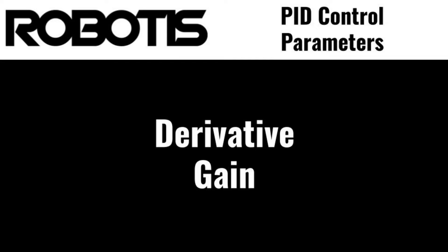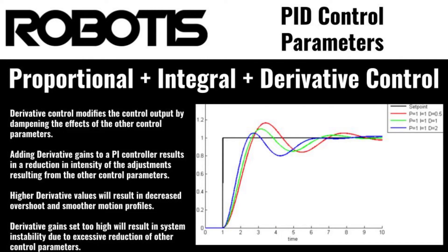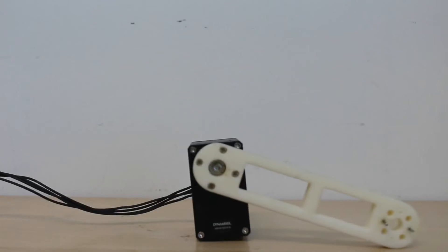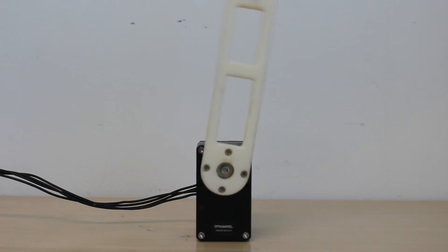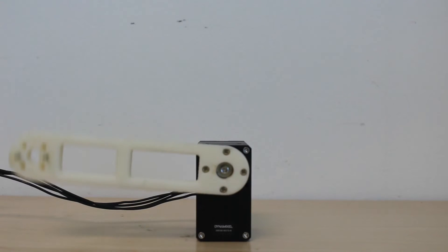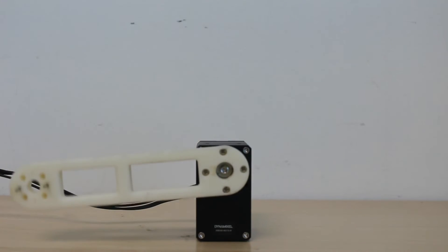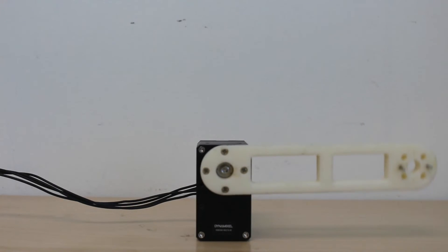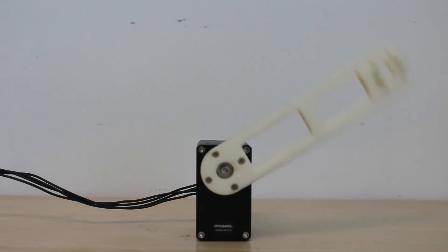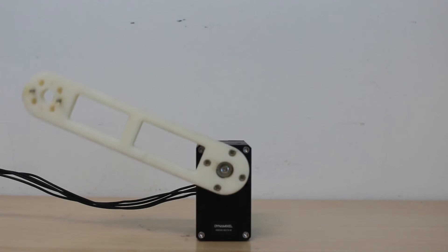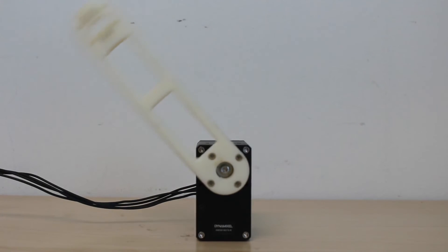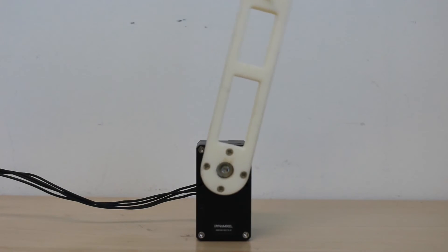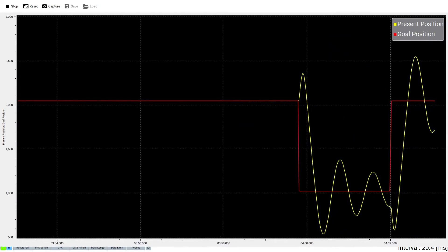The derivative gain can best be described as a smoothing or damping effect applied to P and I gains, in order to create a smoother motion profile and reduce the likelihood of overcorrection or other errors. To see the effect of adjusting D gain, let's set P gain to 80 and I gain to 1000. With these settings, the actuator will oscillate around the desired goal position as it repeatedly overshoots and attempts to correct itself. If we set D gain to 10,000, you'll notice that the initial movement and the oscillation have slowed down significantly. The D gain has modified both P and I gains to reduce the intensity of their effect on the motion of the actuator, allowing for finer-tuned control than either gain by themselves.